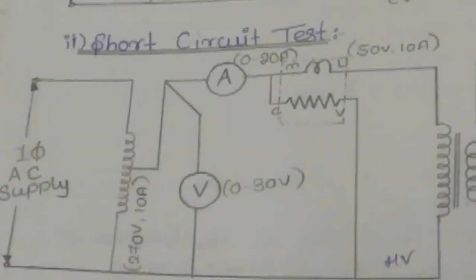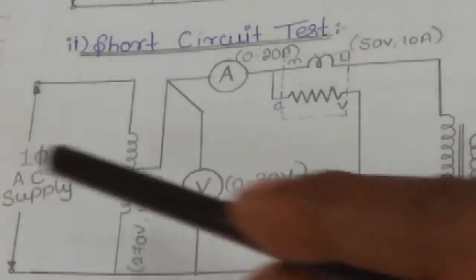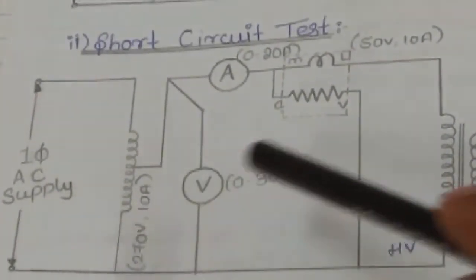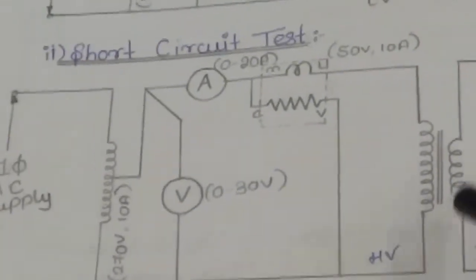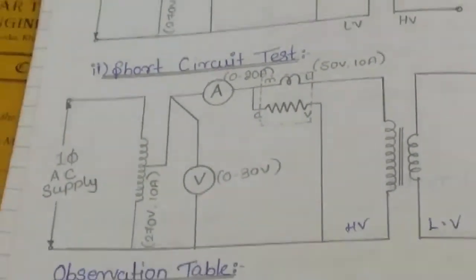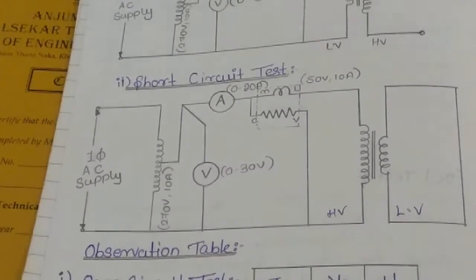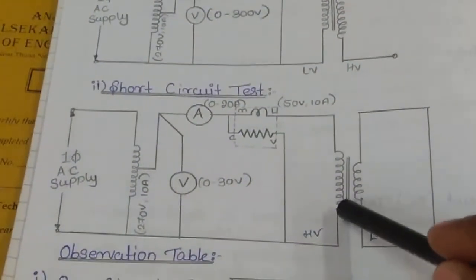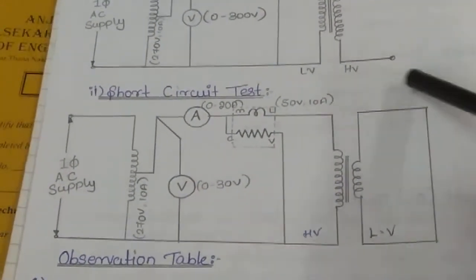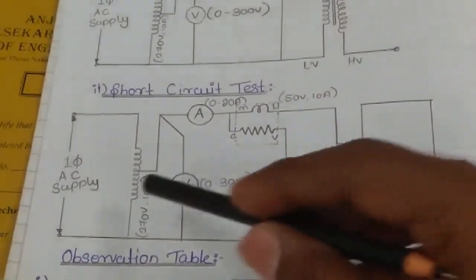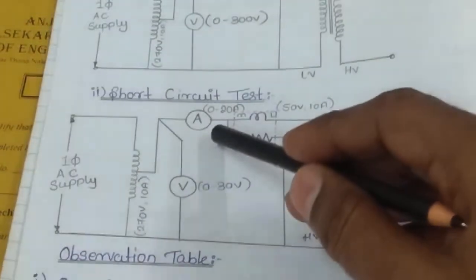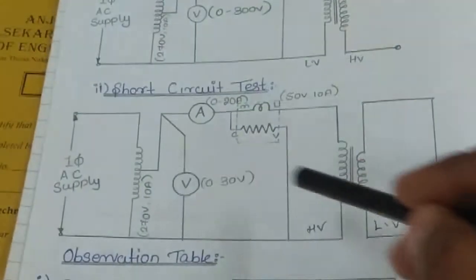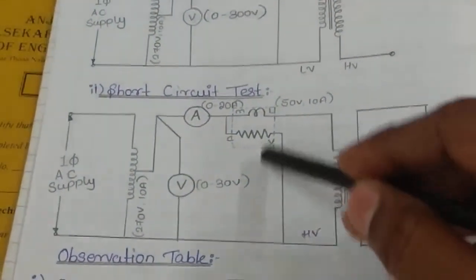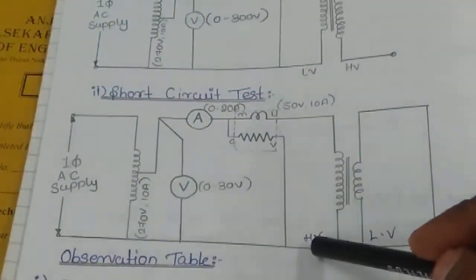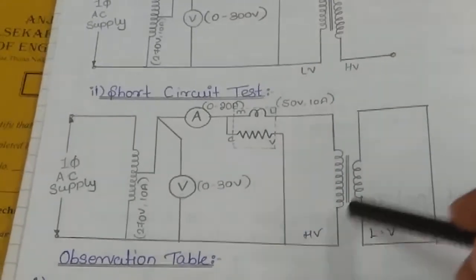Now we will perform the short circuit test as per the given circuit diagram. In this circuit, supply is given to the variac. From the output of the variac, it is given to the transformer. You can see, to the HV side of the transformer, and the LV side of the transformer is short circuited. And the voltmeter is connected in parallel, the ammeter is connected in series after the variac, and the wattmeter is connected in series and parallel to the HV side of the transformer.